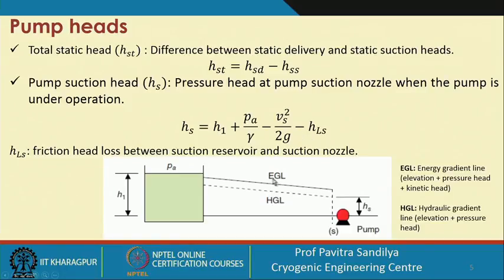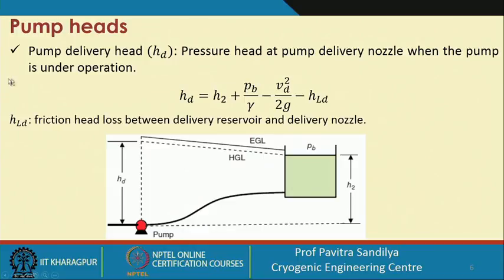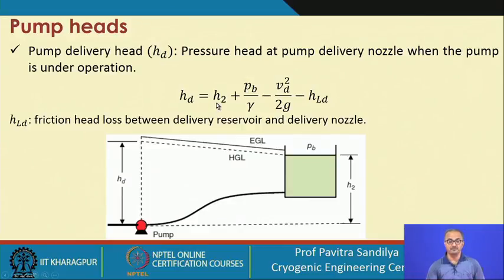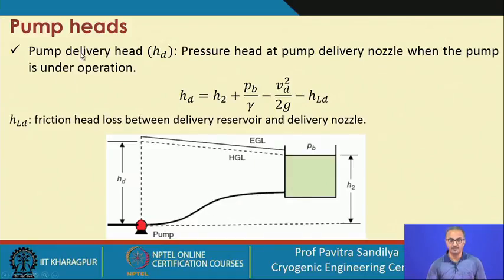In this figure we also have the Energy Grade Line (EGL) and the Hydraulic Grade Line (HGL). The EGL is the summation of the elevation head, pressure head, and kinetic head, while the HGL is elevation plus pressure head. On the delivery side, the pump delivery head is the pressure head generated at the delivery side when the pump is under operation — comprising the potential energy H2, the pressure head, the kinetic head, and the frictional loss in the delivery pipeline.